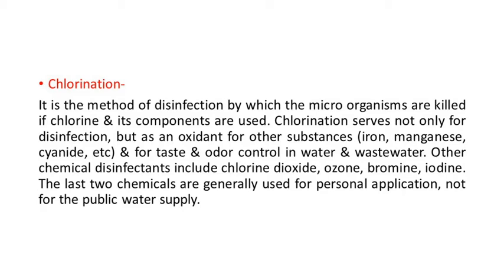If the water has an excessive amount of organic material, sulfide, nitrite, or if the pH of the water is too high, okay, if it is alkaline or acidic, the process of chlorination is affected, so it needs the correct dose of chlorine. So pH is also significant in the process of chlorination.